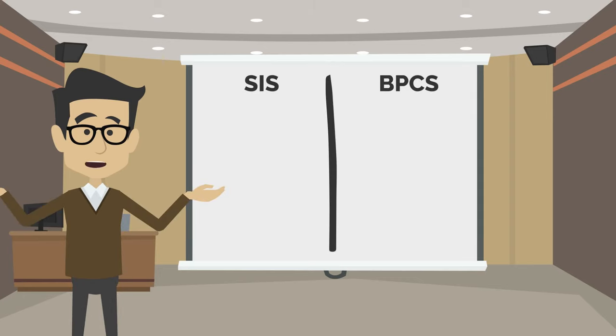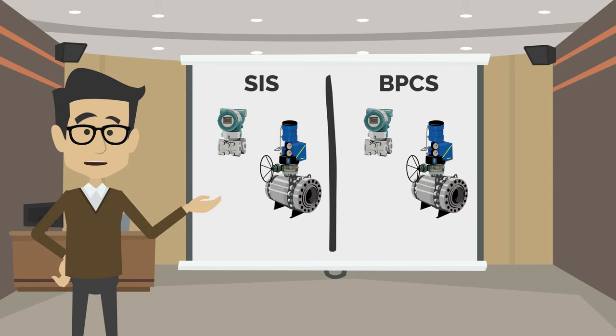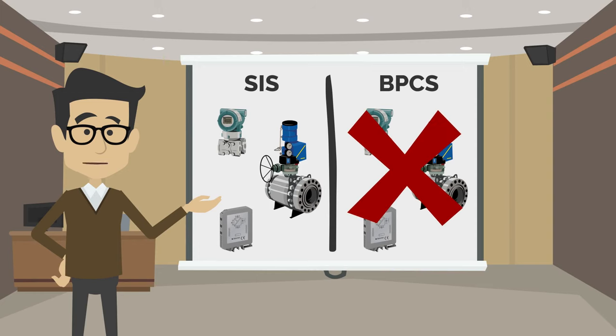The SIS should be independent from the BPCS, with separate transmitters, final elements, and an independent logic solver. Its job is to bring the process to a safe state in the event of a failure of the BPCS.